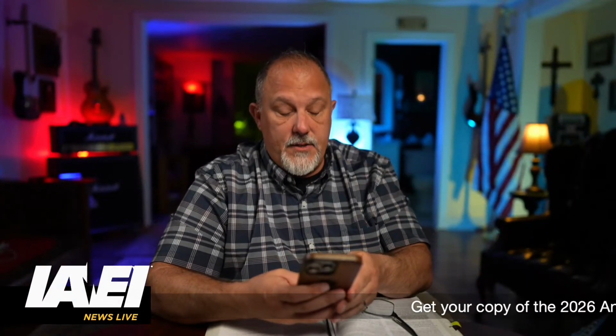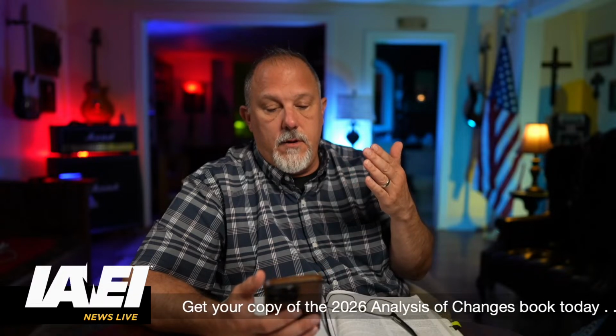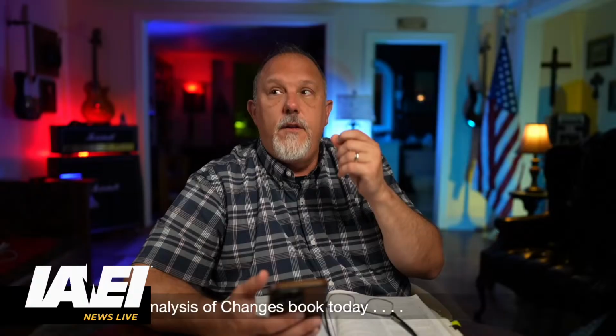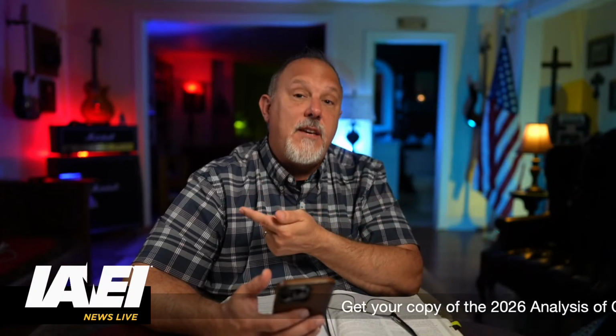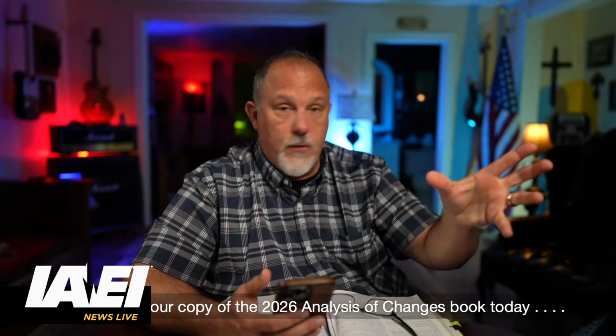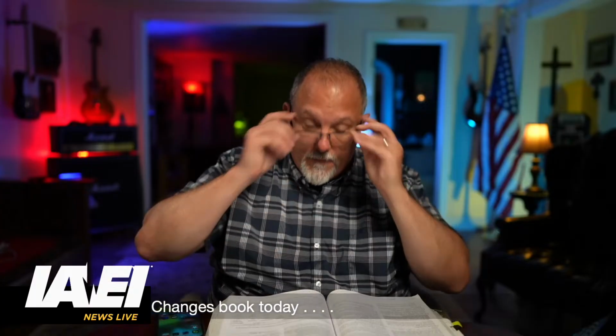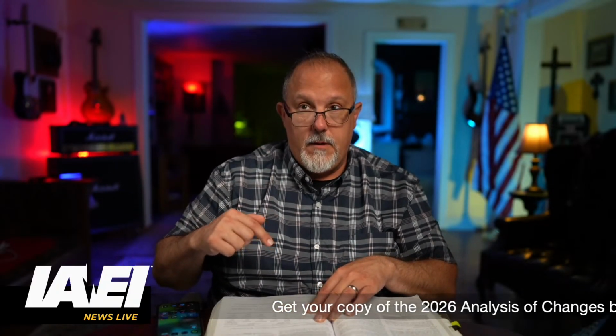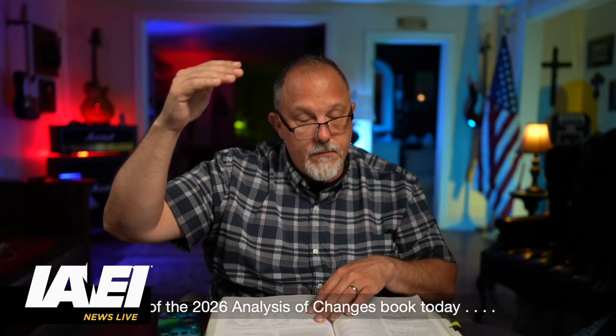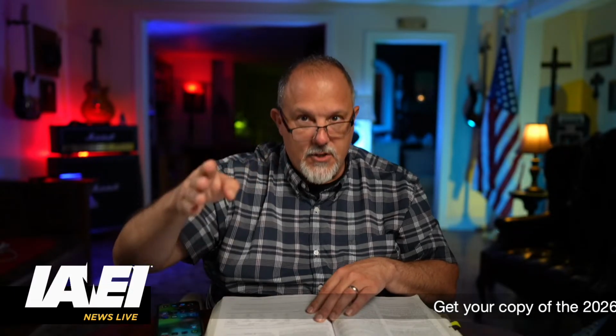So what you can see is that I've got to make sure that I have overcurrent protection and the size of the conductors to handle that 5,000 kVA, because I'll have different full load amps. And if I'm gearing my overcurrent protection off of the full load amps out of table 450.3a, or if you're in the 2026 code, 450.5a, then my overcurrent protective devices could be larger. Ooh, they could be larger. My conductors would have to be larger.